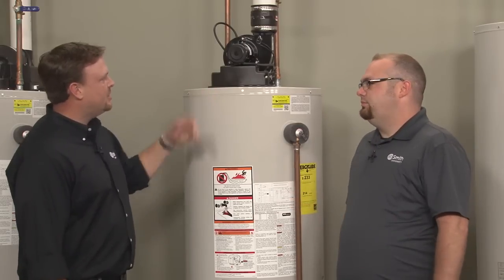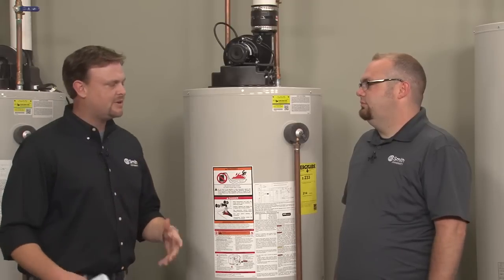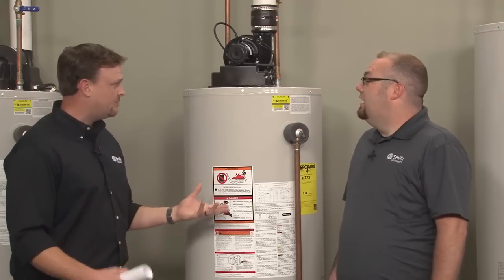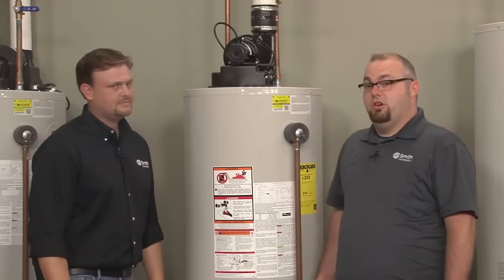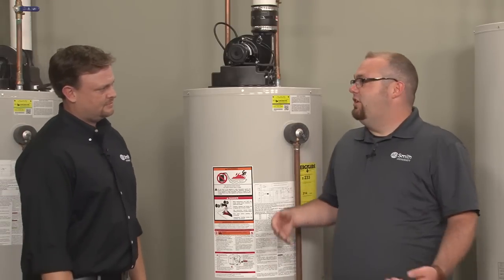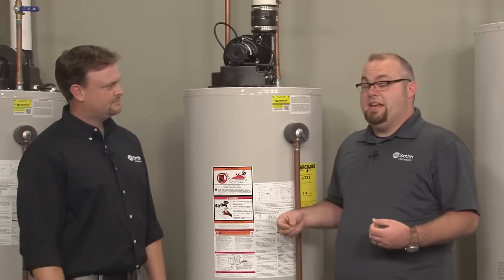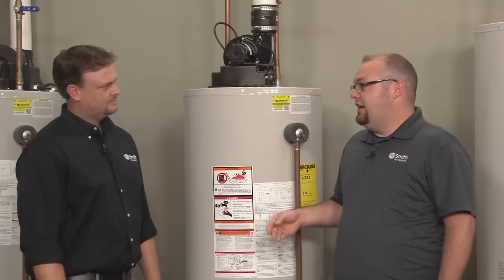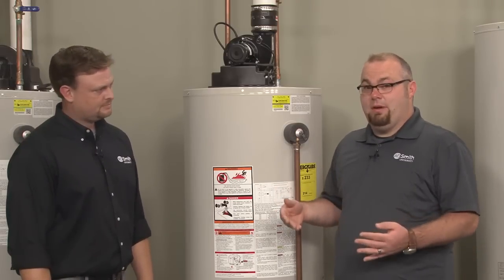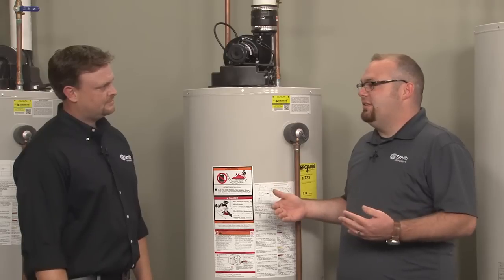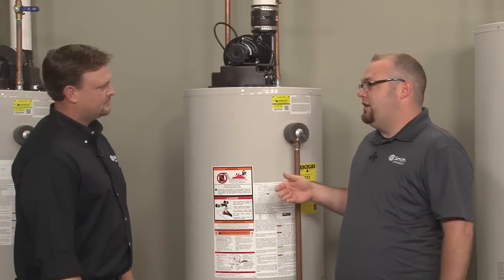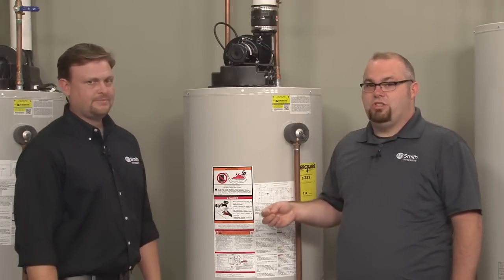Okay. Is there any way to check? Because in some cases it could be the switch itself. So usually what I'd recommend, after everything checks out and I'm sure my venting's clear, that there's nothing in it, I'm sure it's within spec per the manual, I kind of keep it simple. Next thing I check is blower vacuum. But I have to know what the switch activates at.